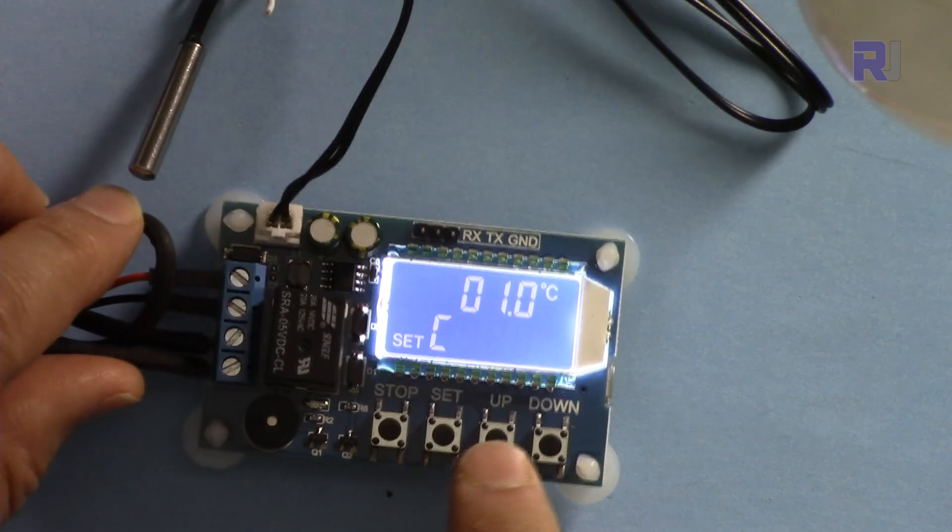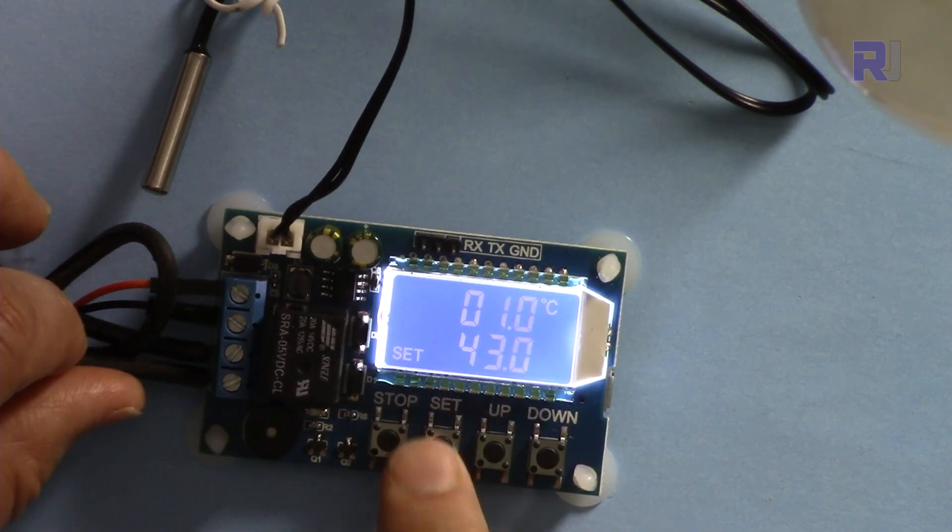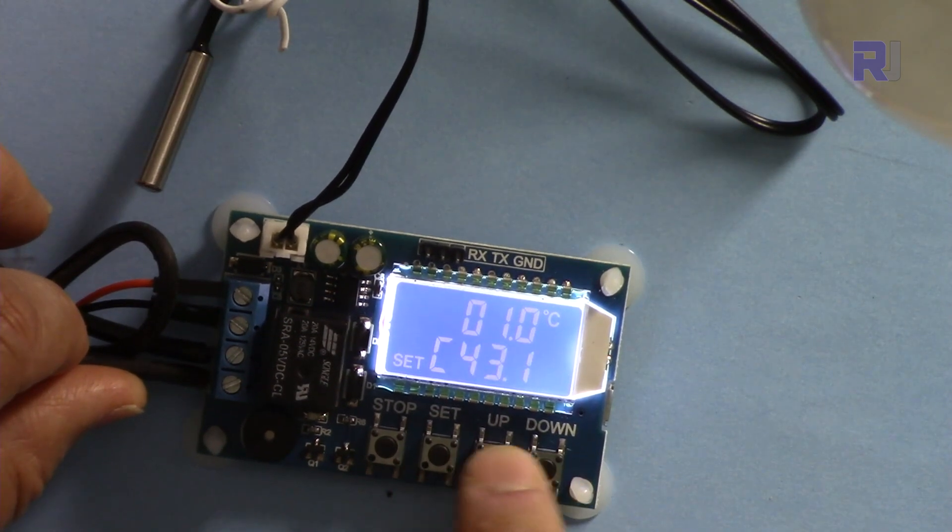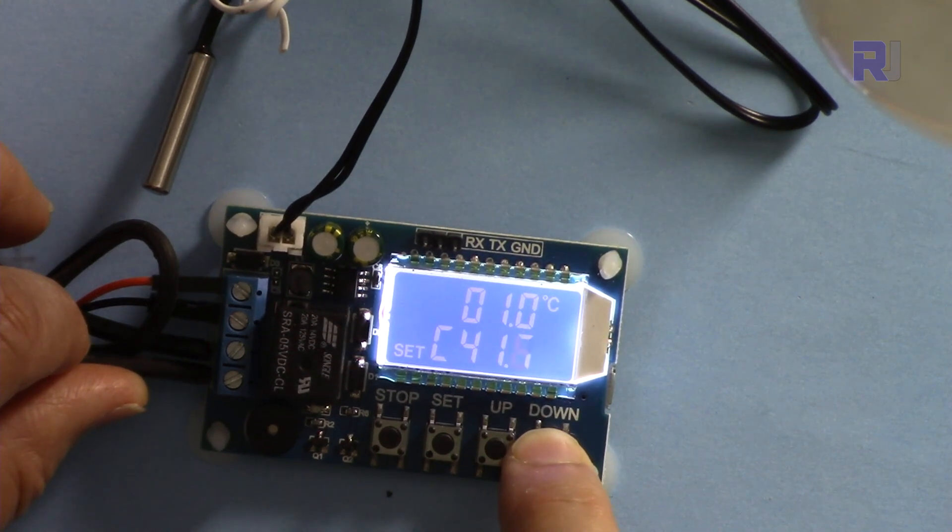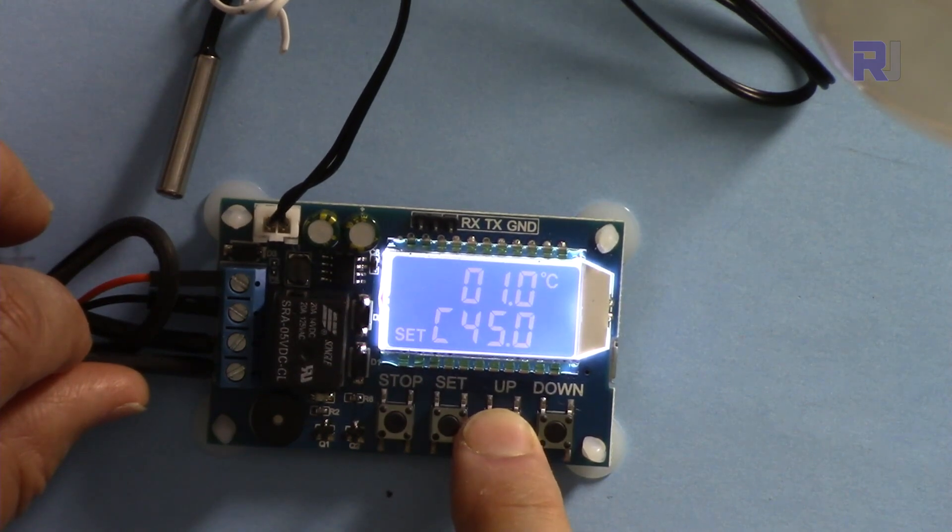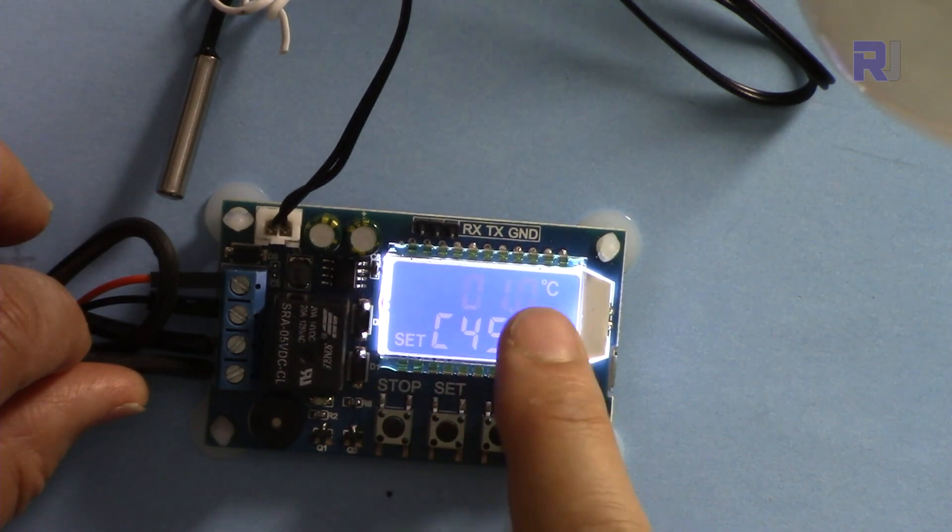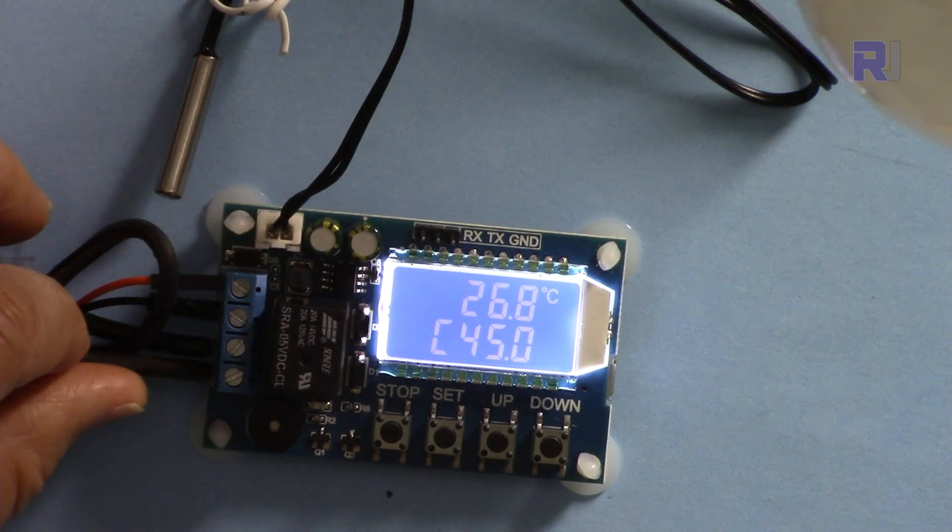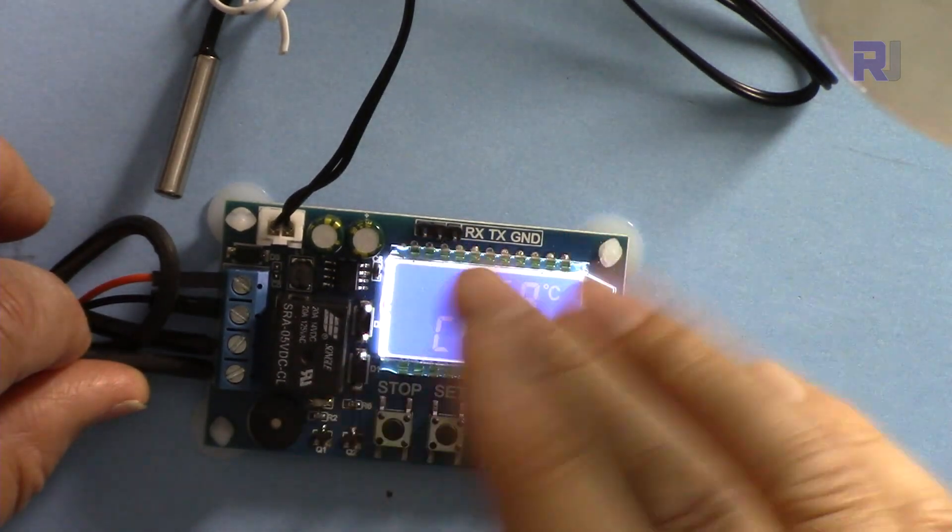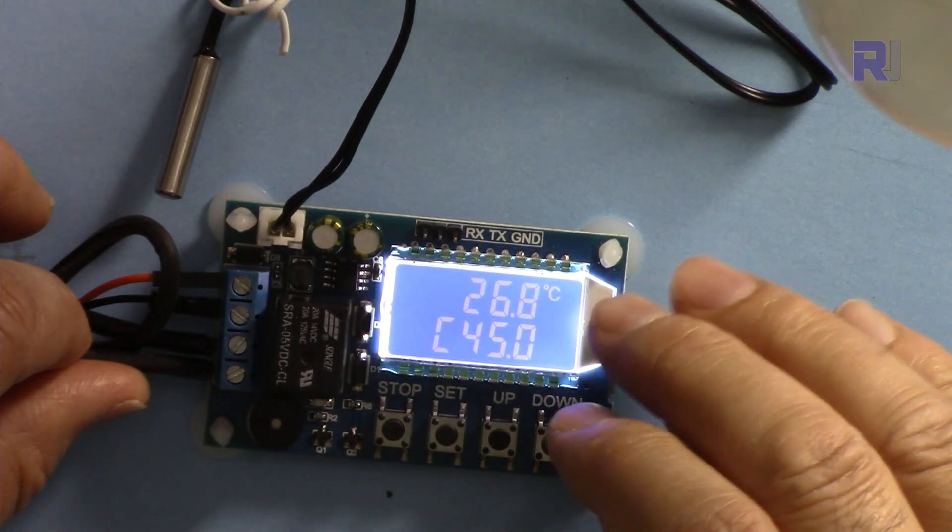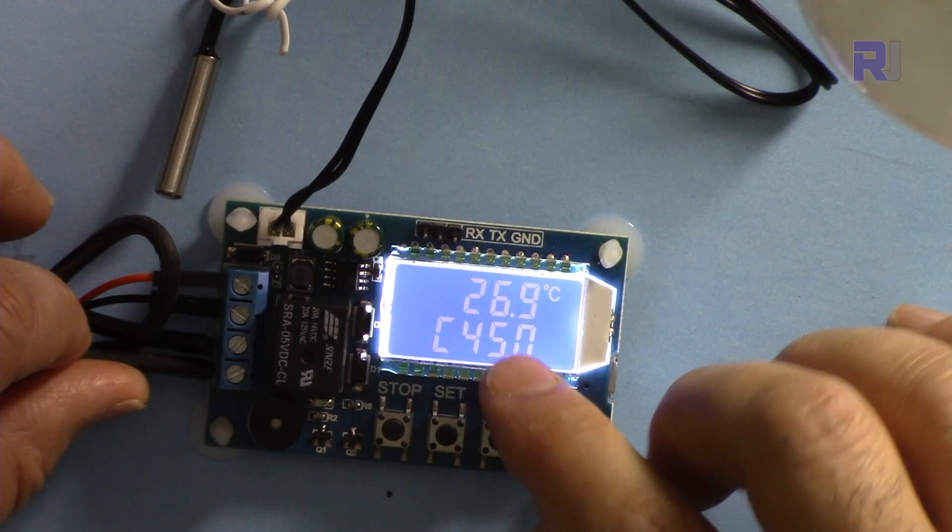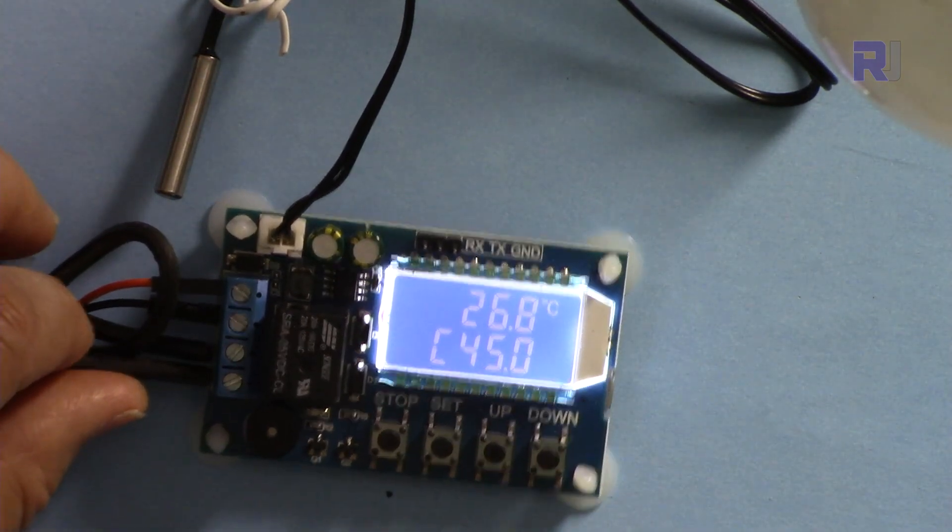I missed the time so let's press this again and press it again so you have few seconds to change it. You can press and hold, it goes down faster or press and hold it goes faster. 45. If I press this here, this one degree Celsius I will demonstrate with example. You have to have some value otherwise the value will fluctuate and relay will turn on and off very quick. So you have to set some kind of value within one degree. It will allow tolerance, so that's the tolerance value.